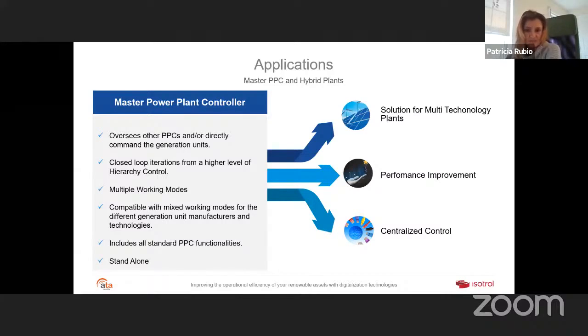A master PPC is basically a controller that oversees the other controllers, but it can also directly command the generation units, bypassing these other controllers. It can manage or model a slave PPC as a single generation point, perform direct open loop control and dispatch corrected set points, or it can work as the ultimate controller and perform closed loop iterations over the slave systems.